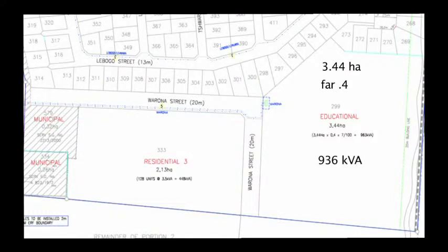So when we've gone through this exercise through all the various areas, we know that for one of these units we probably need about 4 or 5 kVA, depending on the type of unit the developer is going to develop. You add all of this up, and you apply a diversity factor, because not everything is going to happen at the same time. You'll have your peaks and troughs, and it averages itself out.